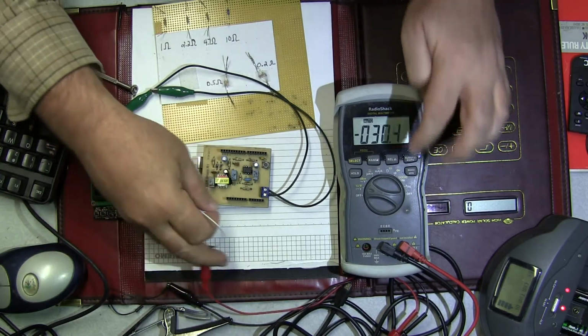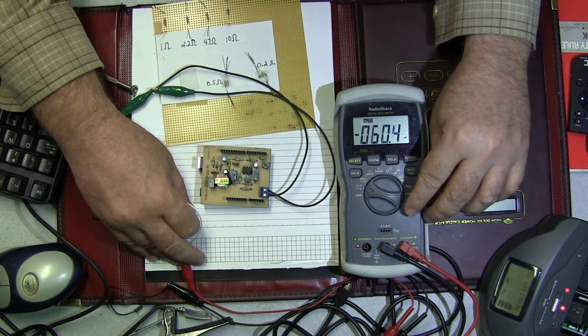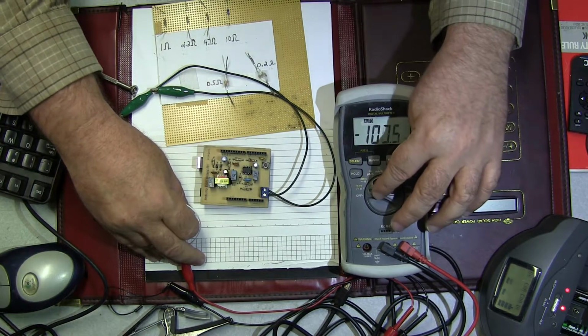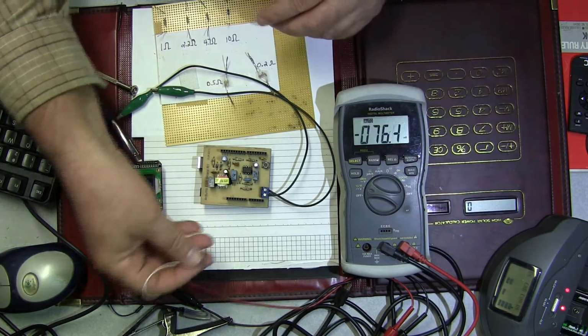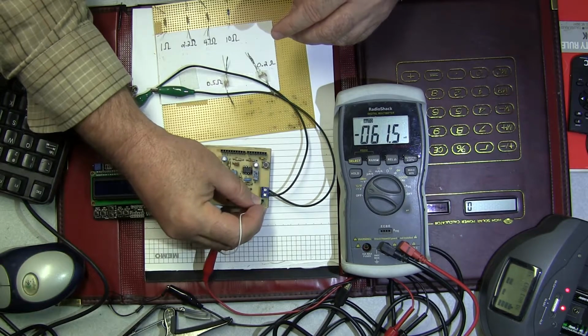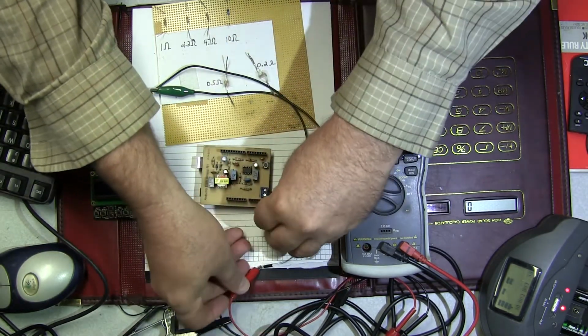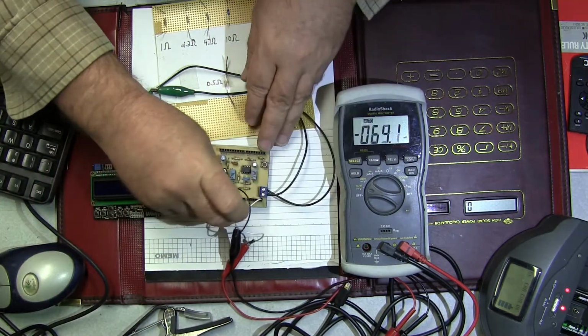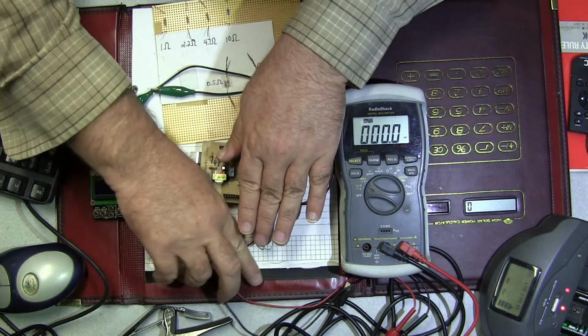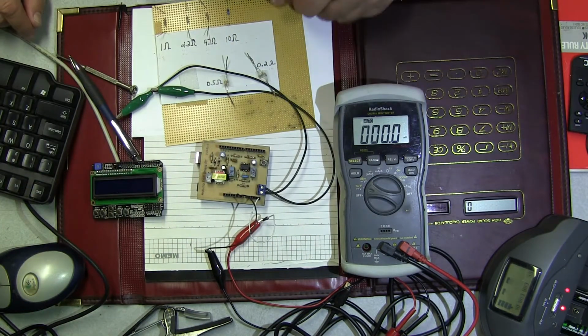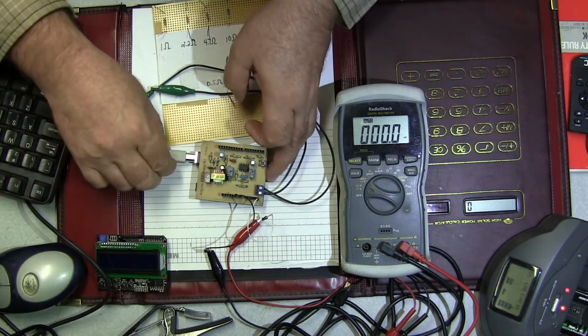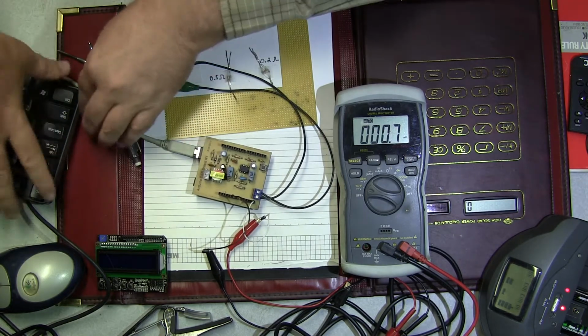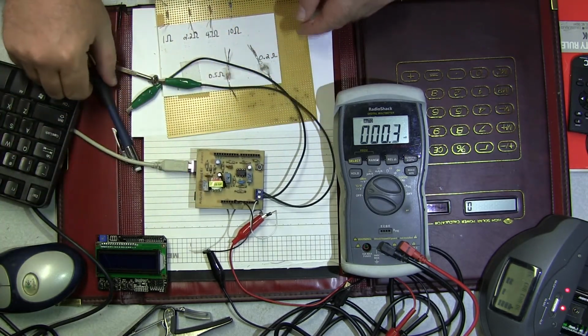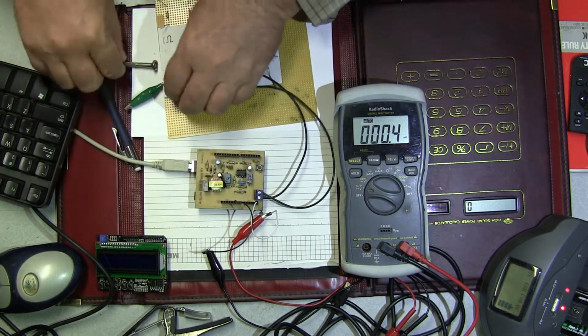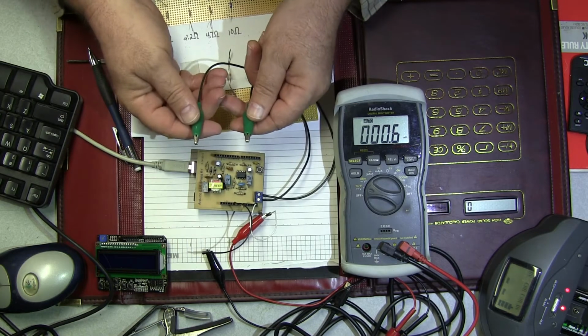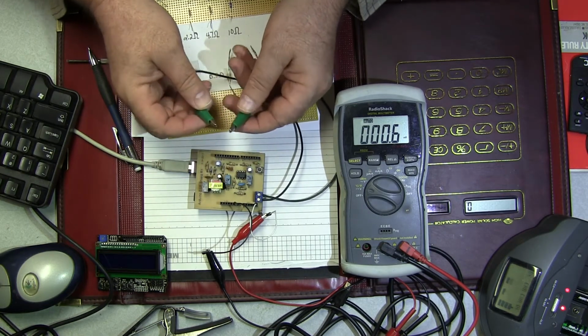The first thing we need to do is get your multimeter and set it in DC voltage. If you have a millivolt setting, that's great. Go ahead and set it up in your millivolt setting, and then you want to put your signal on the A5 pin analog input of your Arduino, and then go ahead and pin out the ground. Okay, there should be no voltage reading. Then if we plug in our Arduino, it's power up there, and we shouldn't see any voltage across these two terminals until we have a device under test between our test leads.